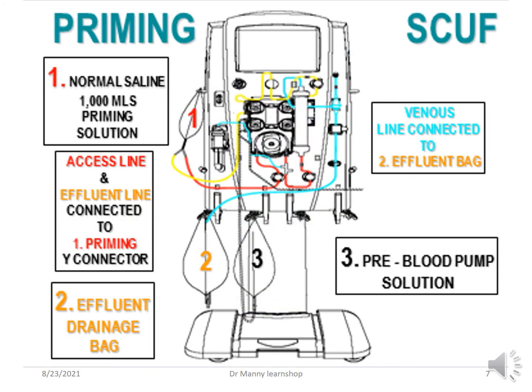When it comes to the priming of the circuit, there's always a normal saline priming solution with or without an anticoagulant. Typically now without an anticoagulant such as heparin, because of things associated with HITS, heparin-induced thrombocytopenia syndrome, certainly in the critically ill patient. So follow the numbers. 1, the priming solution of normal saline, which is connected to the access line and the effluent line, and it primes. It drains into the effluent bag too. You've also got a pre-blood pump solution 3, and it's associated with the venous line and the effluent bag. It primes and gets rid of all the air or anything in the circuit that is not wanted.